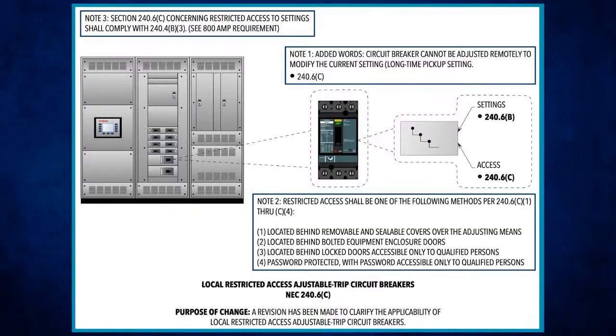100%. So looking at this C, where we deal with local restricted access to adjustable trip circuit breakers, what they did in this section is tell you where you have a circuit breaker that cannot be adjusted remotely to modify the current setting, that's your long time pickup setting. It says that with restricted access, the adjustment means shall be permitted to have ampere ratings equal to the adjustment current setting, which is your long time pickup setting. And it says that to achieve this restricted access, you have to apply one of the following methods.